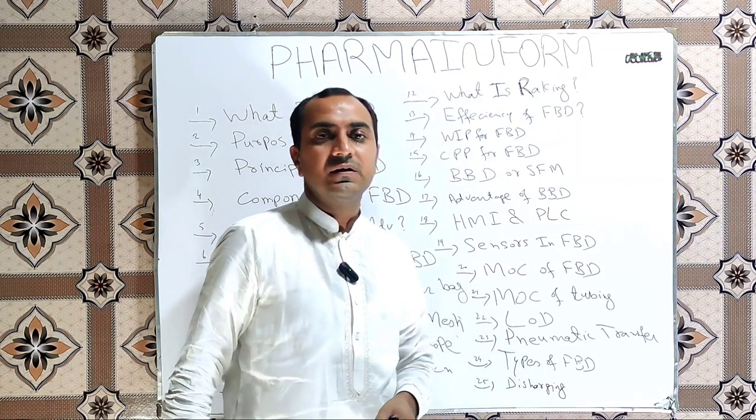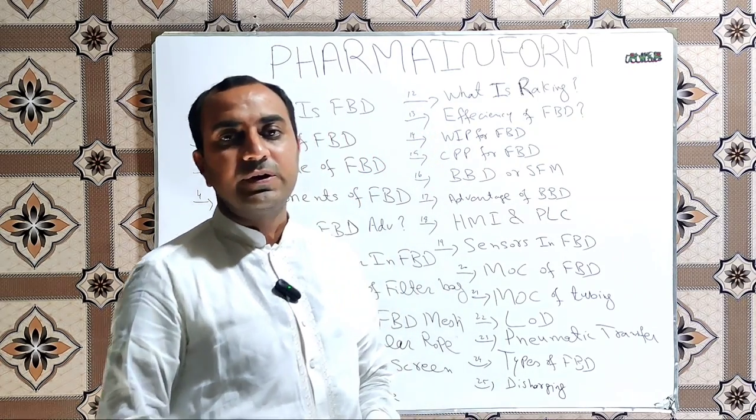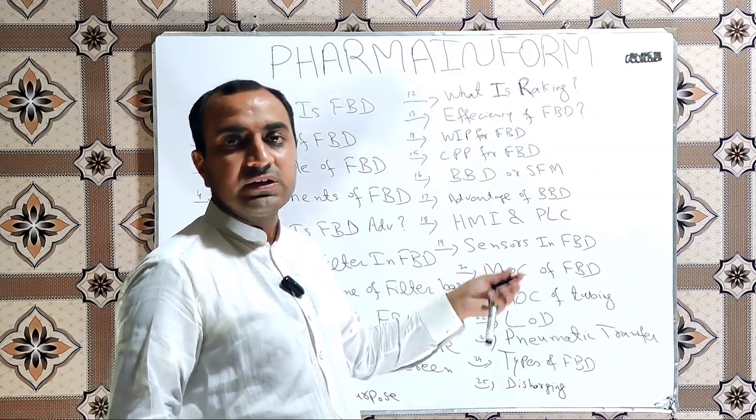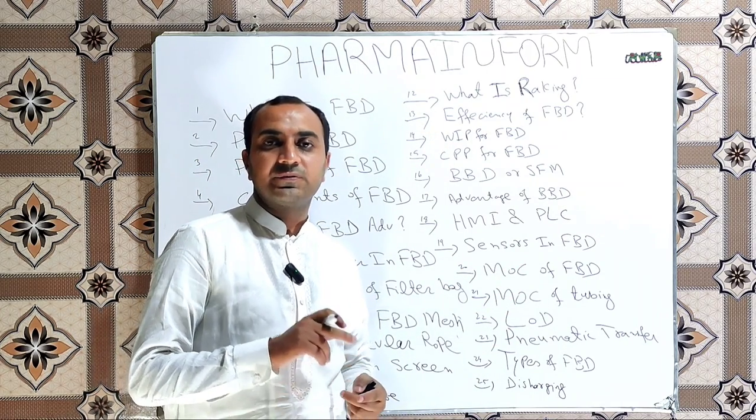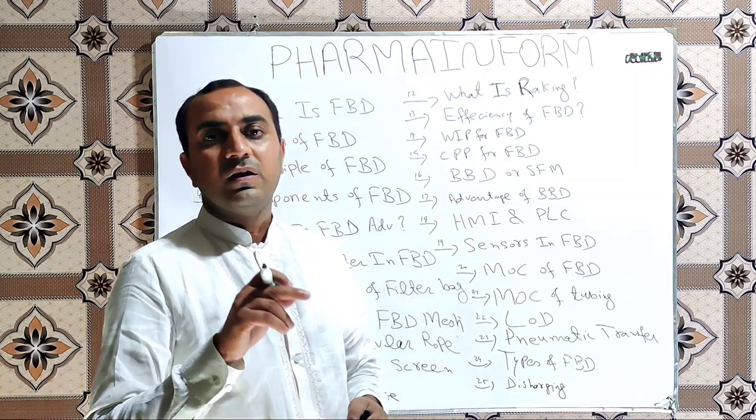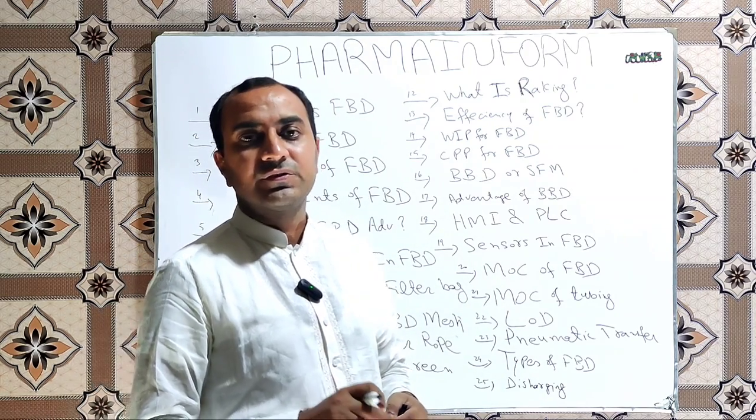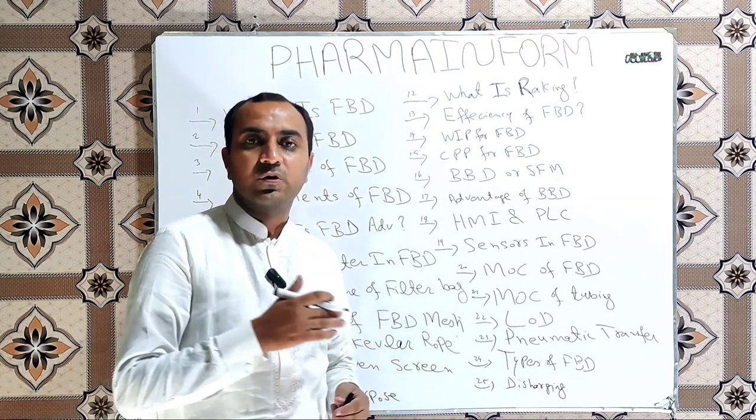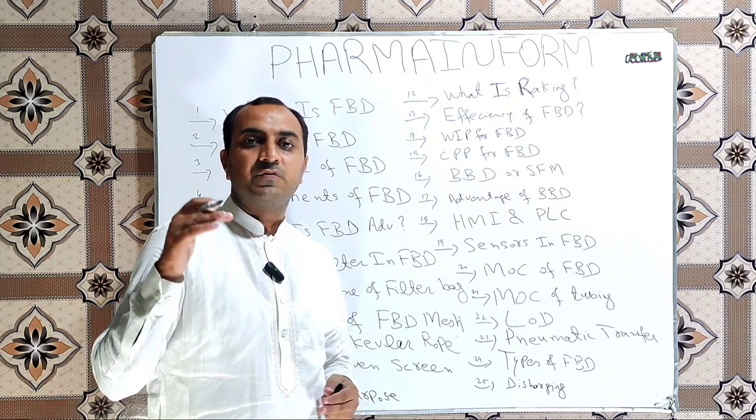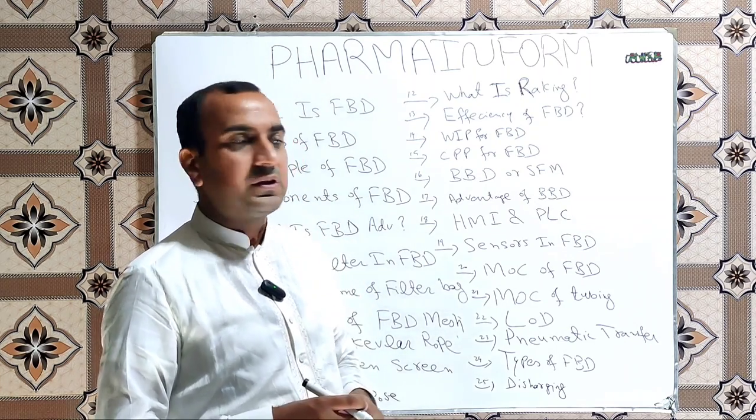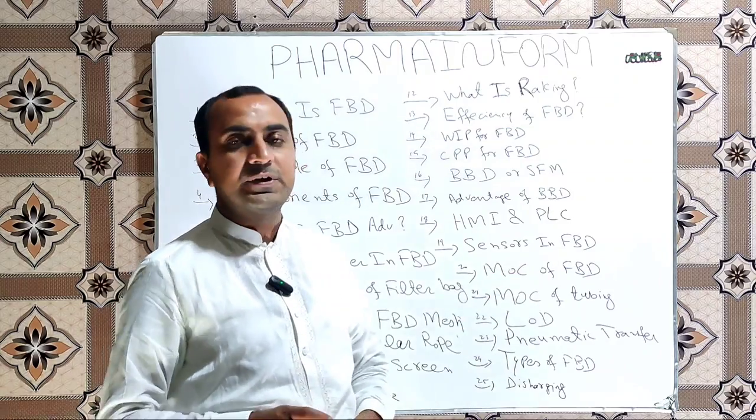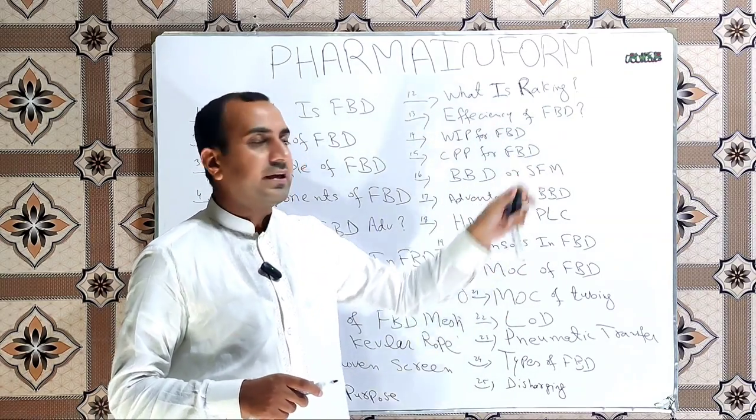What are the types of sensors in FBD? Usually in the FBD following sensors are installed: temperature sensors, pressure sensors, airflow monitoring sensors, product trolley not in place sensor, and filter position alignment sensors. These are some commonly installed sensors in the FBD and also one is the SFM.